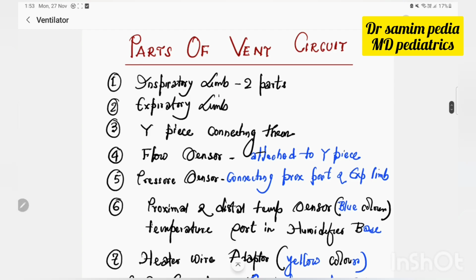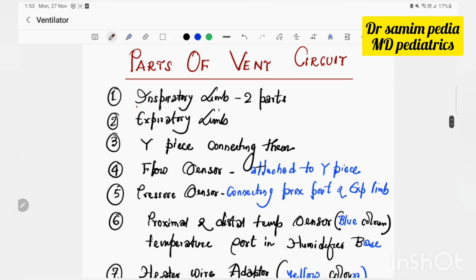Number one is the inspiratory limb. The inspiratory limb has two parts. Part one is connected between the inspiratory port in the ventilator and the humidifier, and part two is connected between the humidifier and the Y connector. Expiratory limb. The Y piece connector connects the inspiratory limb and the expiratory limb. Fourth one is the flow sensor, which is present between the Y piece connector and the ET tube.